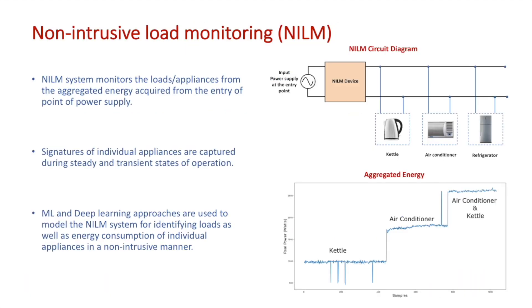The NILM system monitors the events and energy consumption of the loads from the aggregated energy acquired from the entry point of the power supply. In this process, we first need to learn the signatures of the individual appliances that are captured during the steady state and transient states of operation. Then we feed the features captured from these states to machine learning and deep learning approaches to model the system for identifying loads and estimating the energy consumption of individual appliances in a non-intrusive manner.